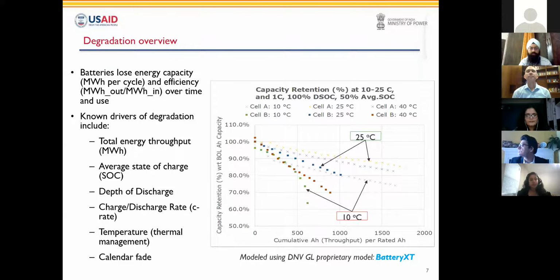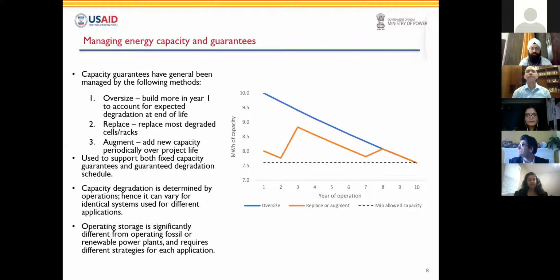Moving forward with the design considerations. In terms of designing utility scale systems for a contract, typically the developer is held to a capacity guarantee that they need to maintain for the whole contract term, and they need to account for degradation while sizing the system. They do this using one of three strategies.